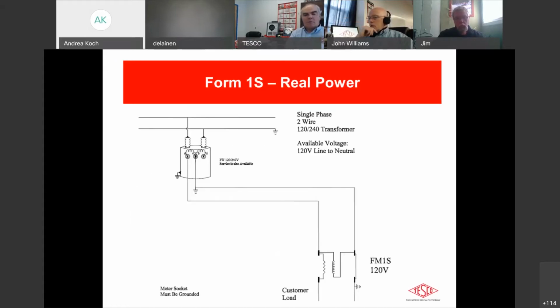So here's some examples, and I'm going to go through a bunch of these examples. It's going to take a while, and we have some of our folks with outside metering experience who are going to give some examples of where some of these meter forms are used. But in general, I'll talk through the schematics of the different meter forms and how they're applied in the field, and then how we simulate that energy into that meter for meter testing using the phantom loading that we just spoke about.